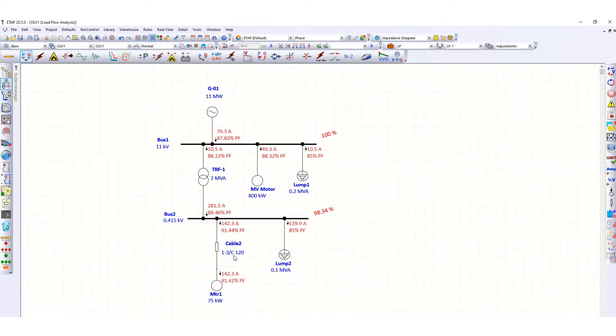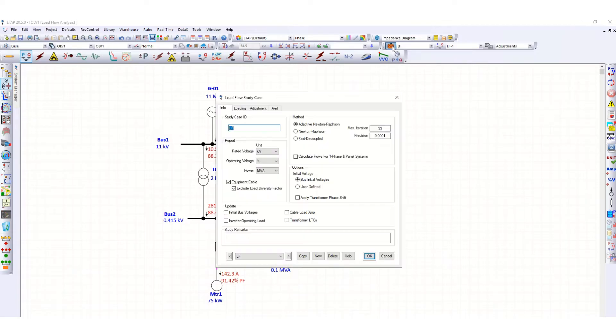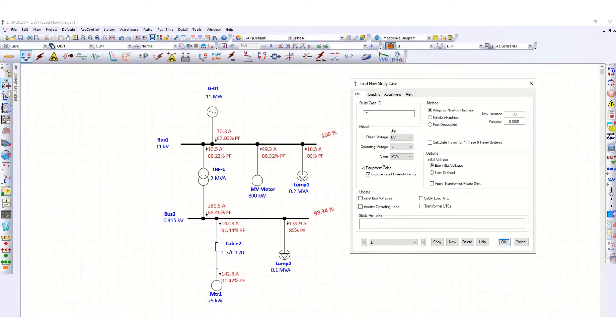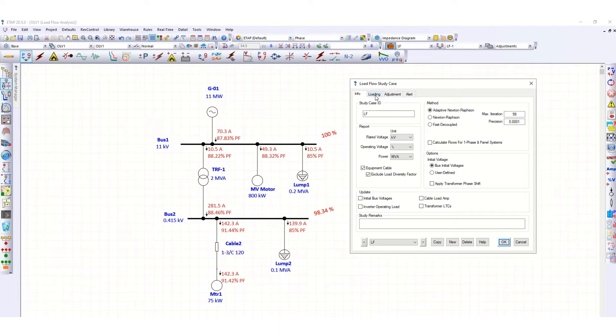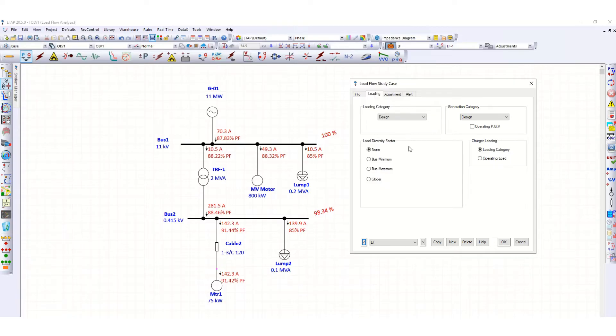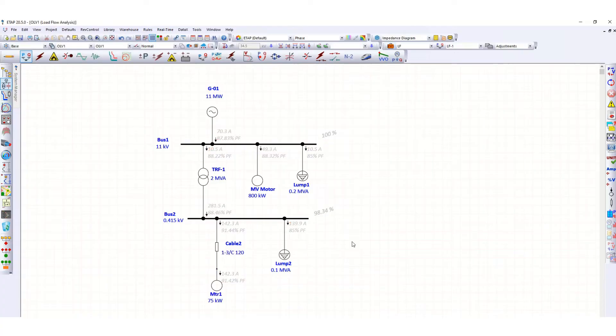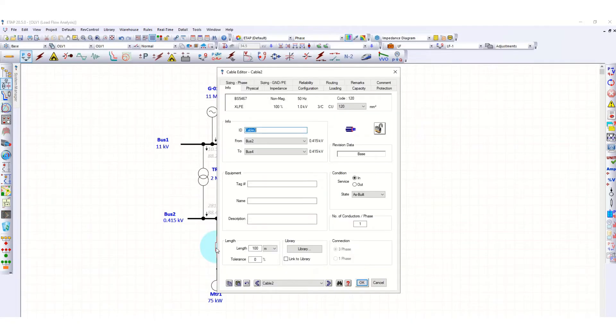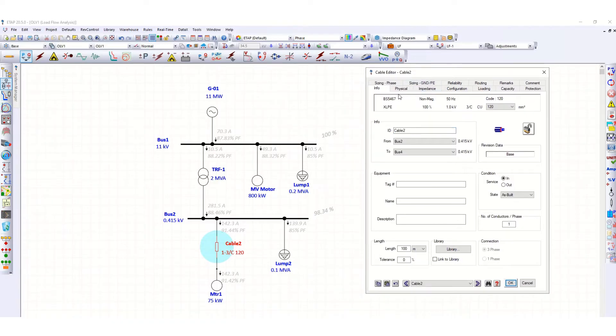The cable size we have preliminarily considered is single run three core 120, number of conductors one. Now go to edit study case in edit mode. Check the option to update the cable load amps — this will update automatically. The loading fields are not required here, so click OK, then double-click this cable.